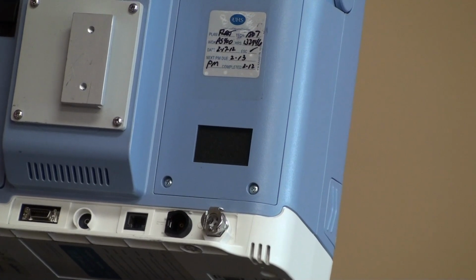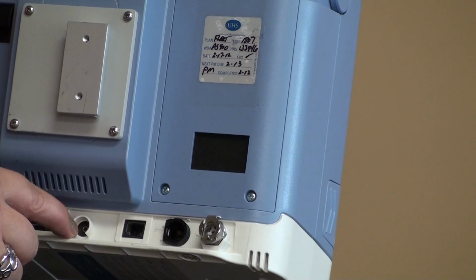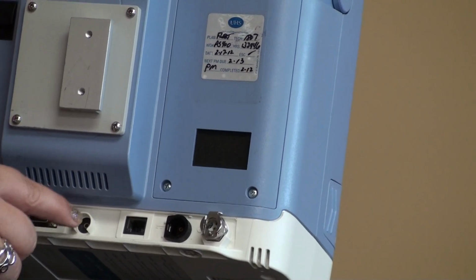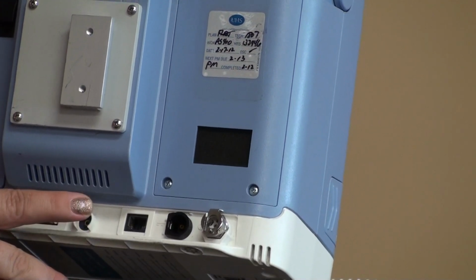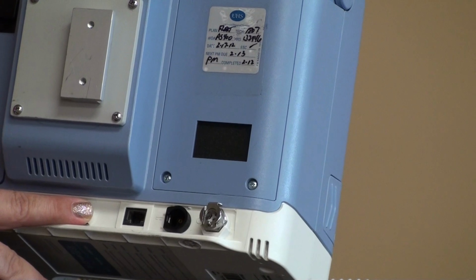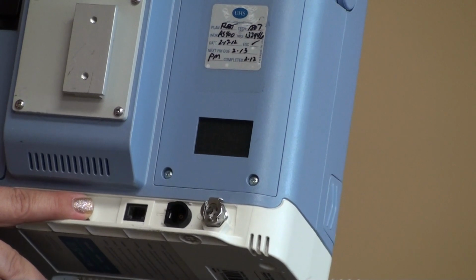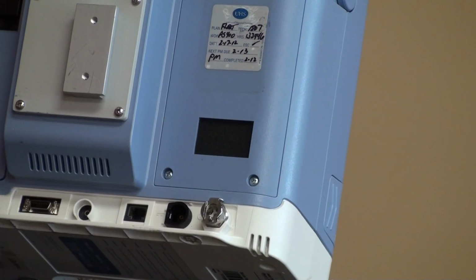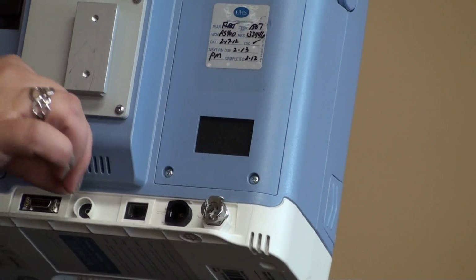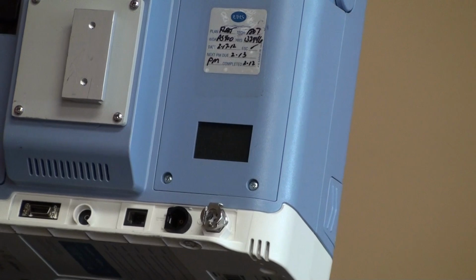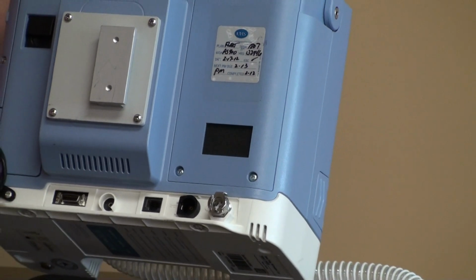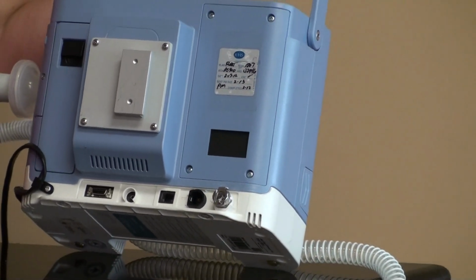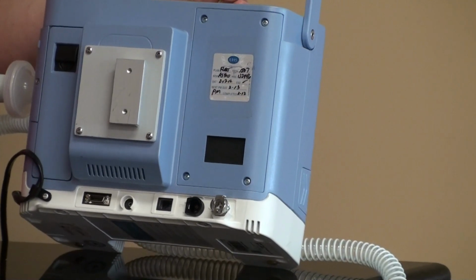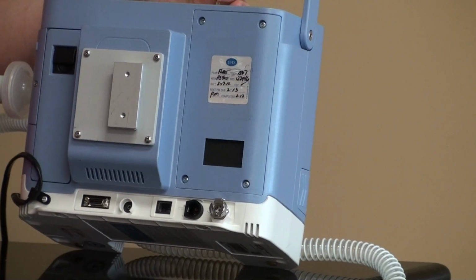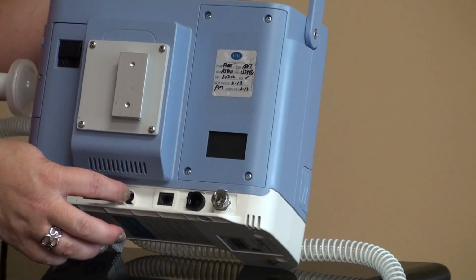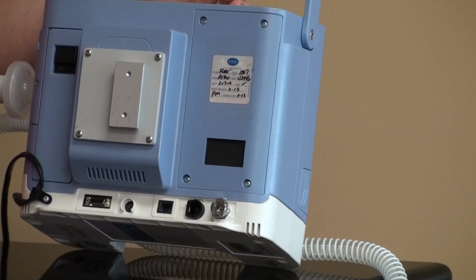And then you're going to have your D, which is remote alarm connector and audio sound, which is located right here. This is where you don't want to have something blocking over it, like a cotton ball or something taped on the back, so that you can't hear the alarm really well. This is also where you can plug in a port with up to 300 feet worth of cord and a little box that has a remote alarm. You might be asked by the family not to be in the room, or they want you down the hall or something like that. Well, this way you know when the alarms are going off because you have this remote alarm with up to 300 feet of cord attached to it.